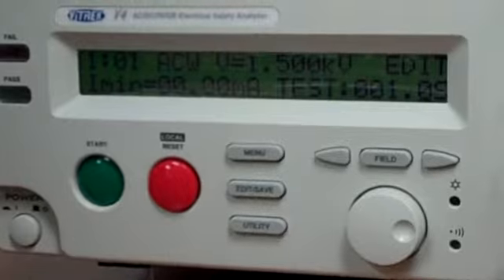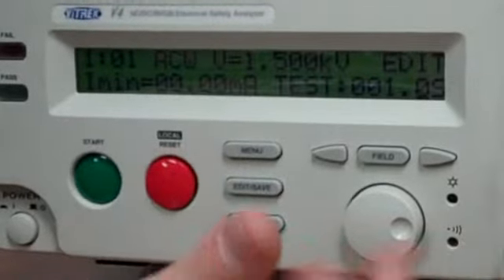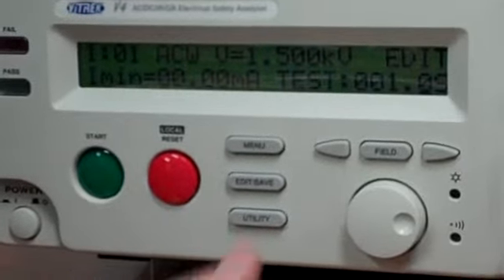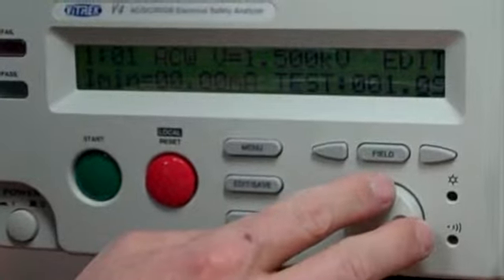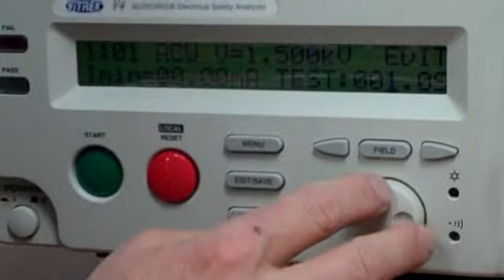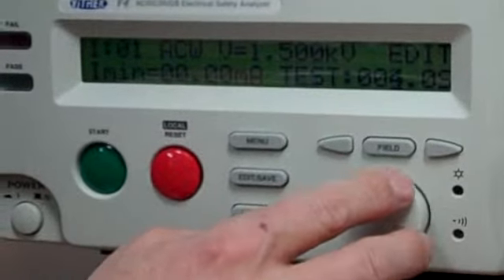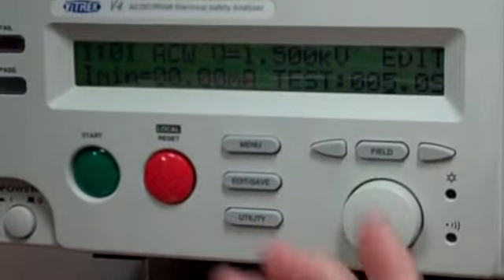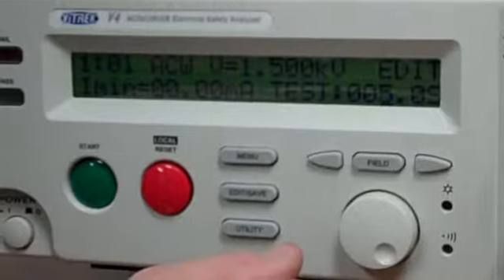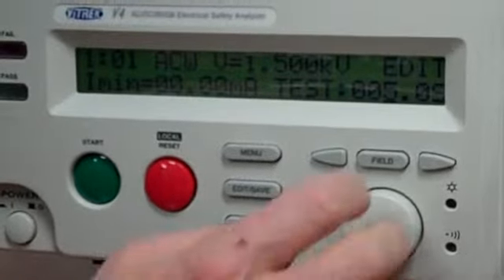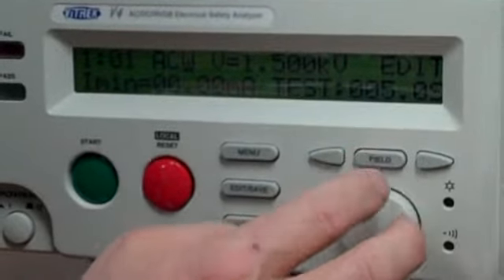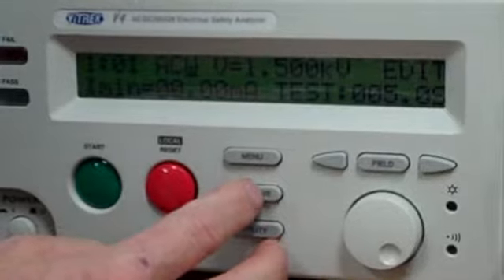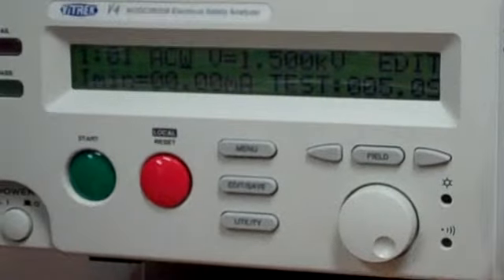And then the test time, that's how long we're going to dwell on the given test. For this demonstration purpose, we'll use 5 seconds. So go right here, 1, 2, 3, 4, and 5. That completes all the test parameters that we need to do for an AC high pot test. And we hit the save button here to save that particular step.